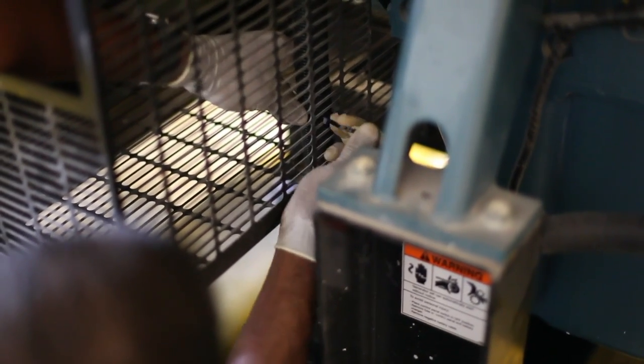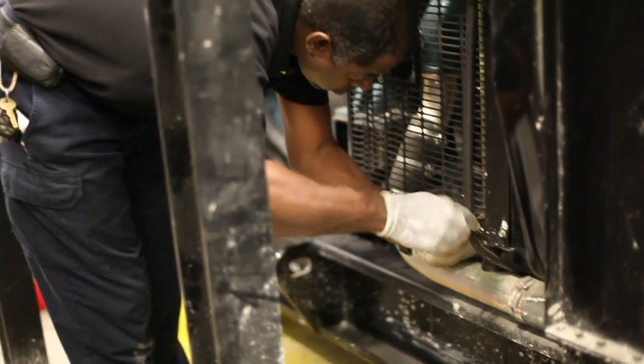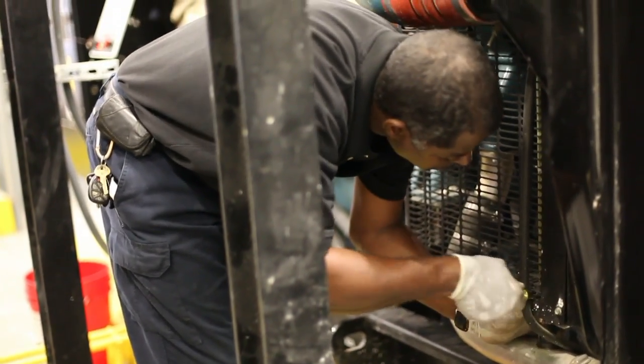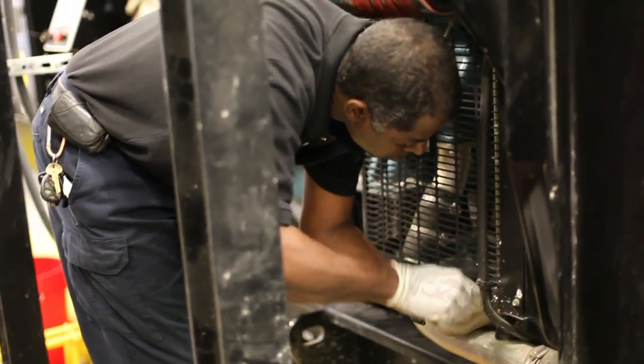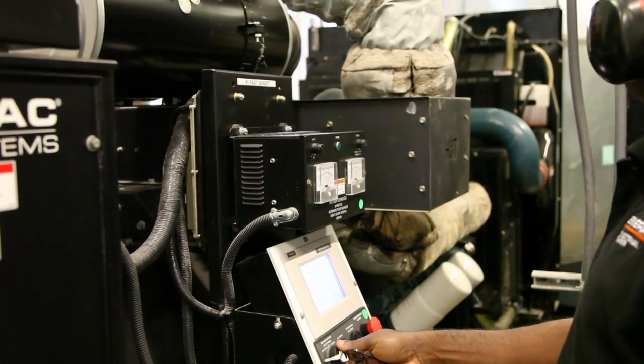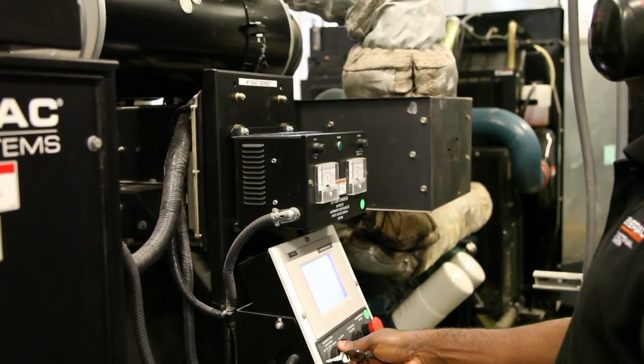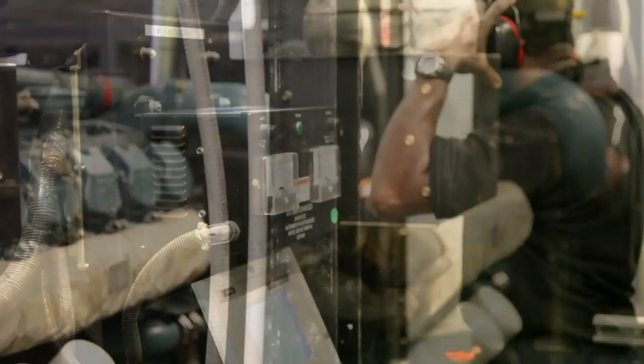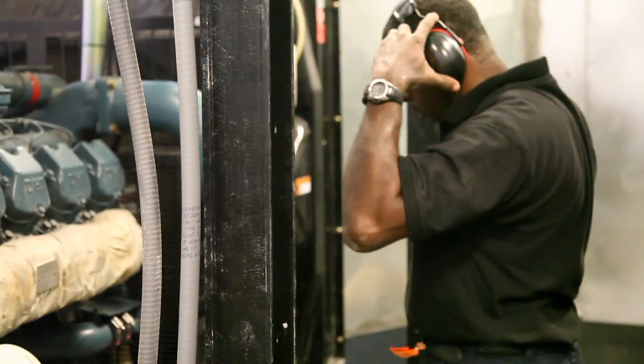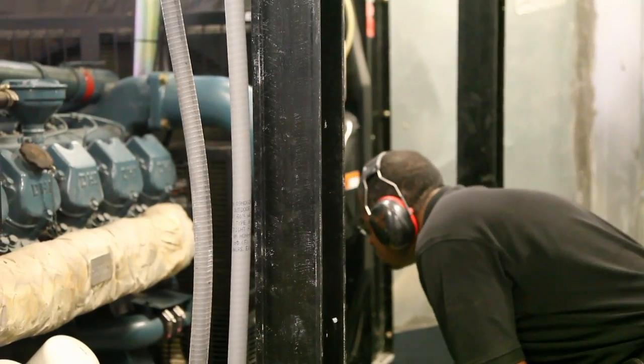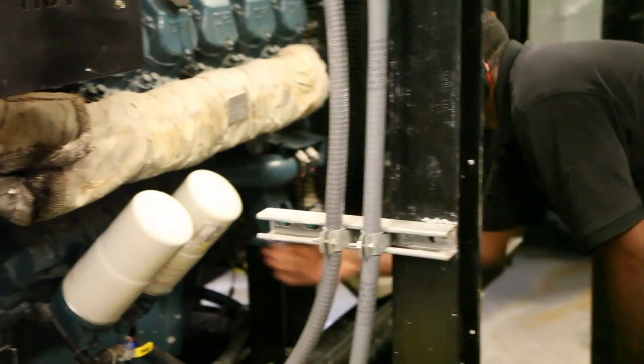Belt tension and their condition are checked. Any belt is replaced if found in poor condition or it has reached the manufacturer's recommended change period. The condition of the fan and belt guards are checked, and any signs of deterioration noted for immediate or future change. The technician starts the generator after all checks and replacement of the coolant components to check for any hot leaks.